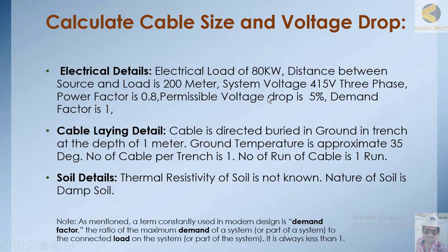The length of the cable is 200 meters, system voltage is 415 volts three-phase, power factor is 0.8. As seen in previous lectures, a cable has two components — resistance and reactance — and depending upon power factor, voltage drop appears, so we use power factor here. The permissible voltage drop is 5% and demand factor is 1.